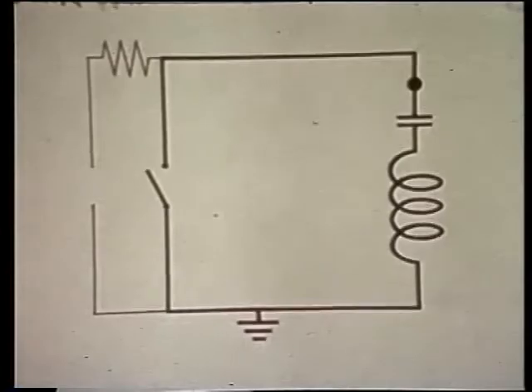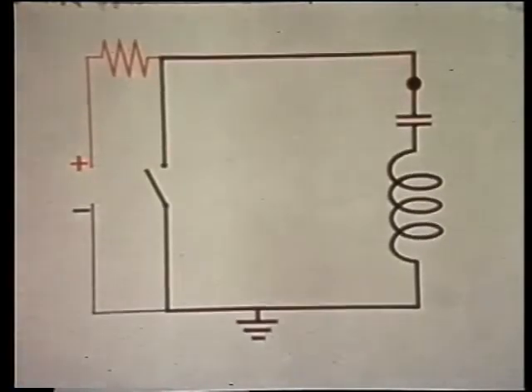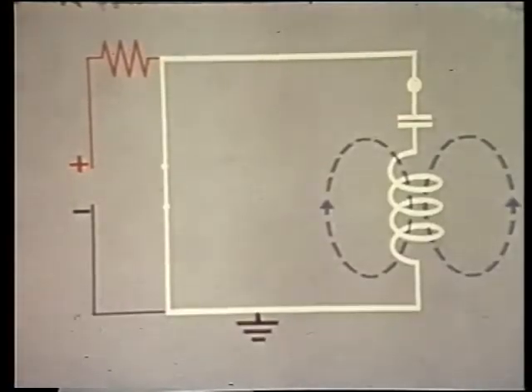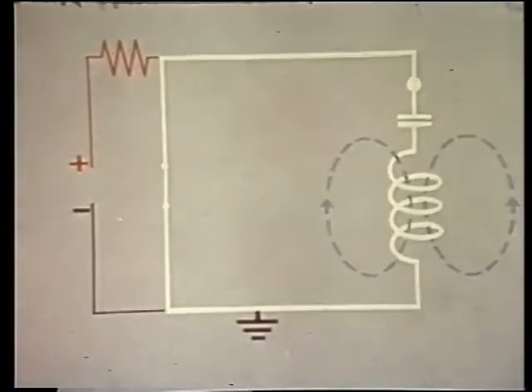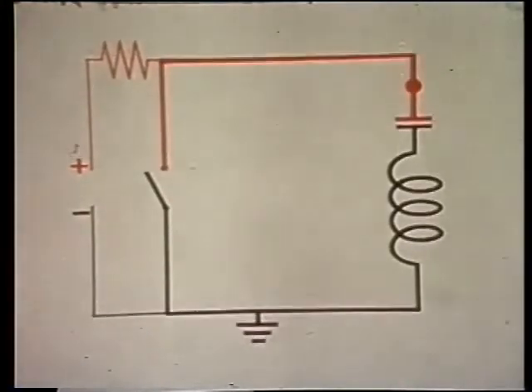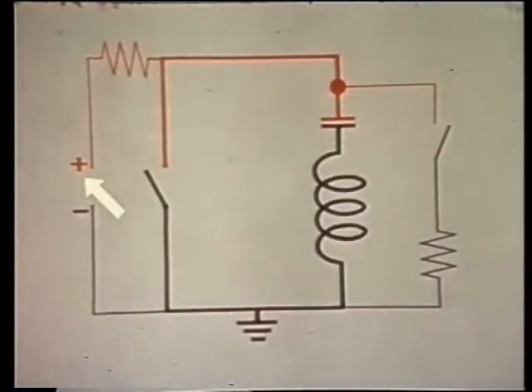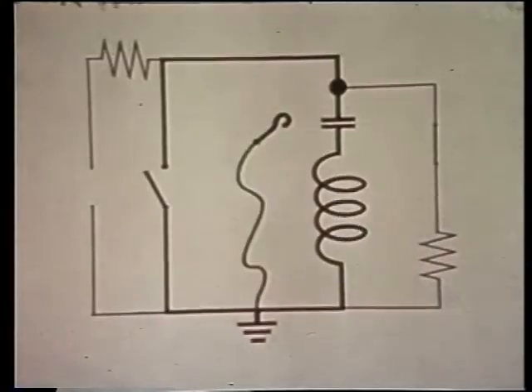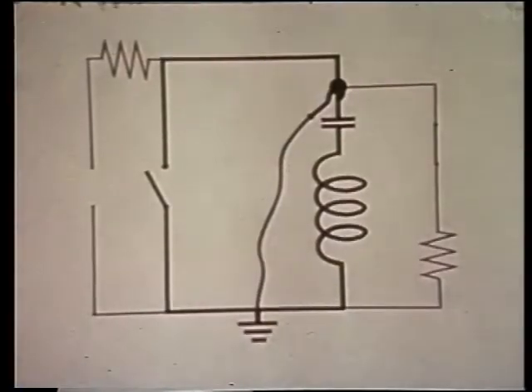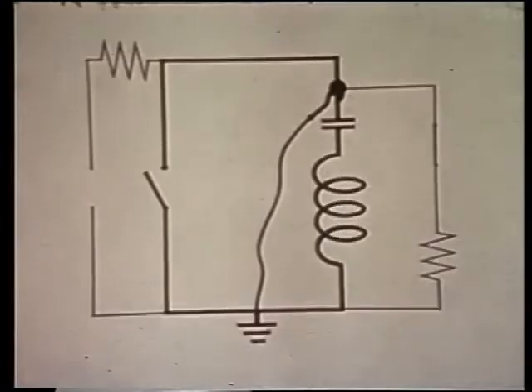Here's the circuit and this is how it works. On each firing, a pulse is fed through the coil. After each shot, the capacitor automatically recharges. When we want to enter the cage, the main isolator cuts off the supply and the charge is automatically dumped. The capacitor is finally earthed with the earthing stick. As the coil is earthed at one end, it's automatically safe.